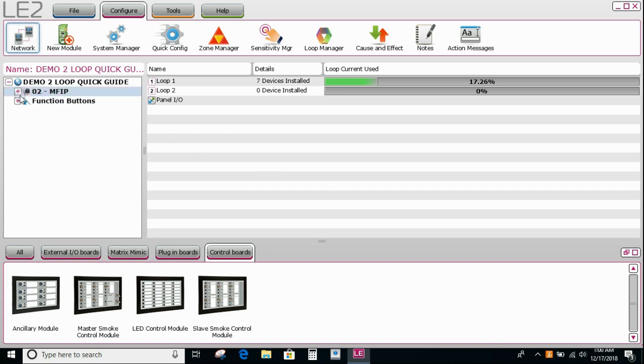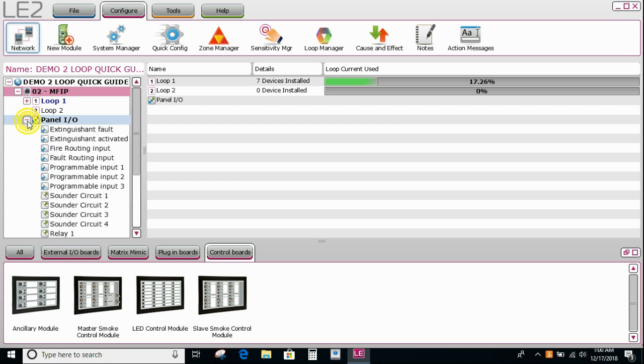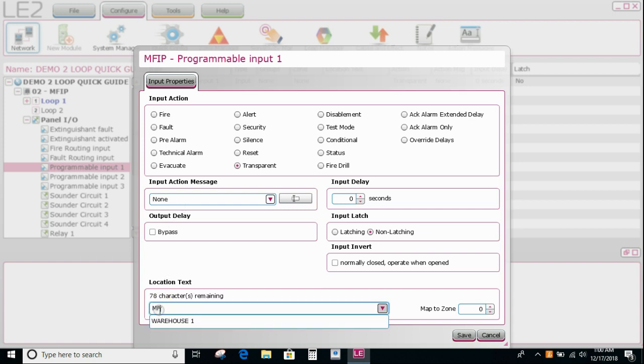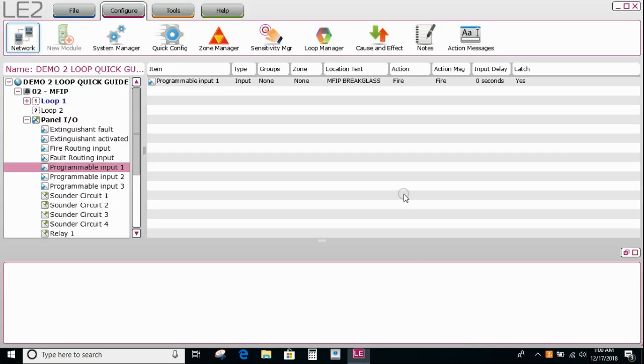So the next thing I might do is set up the call point in the front of the panel. So I open up or expand the node, go to my panel IOs and expand that. And the call point is typically wired into programmable input number one by default. So we're going to say main FIP break glass. I'm going to say bypasses all outputs. I change it from transparent to fire. Very important that. And then we go to latching. And then say save.